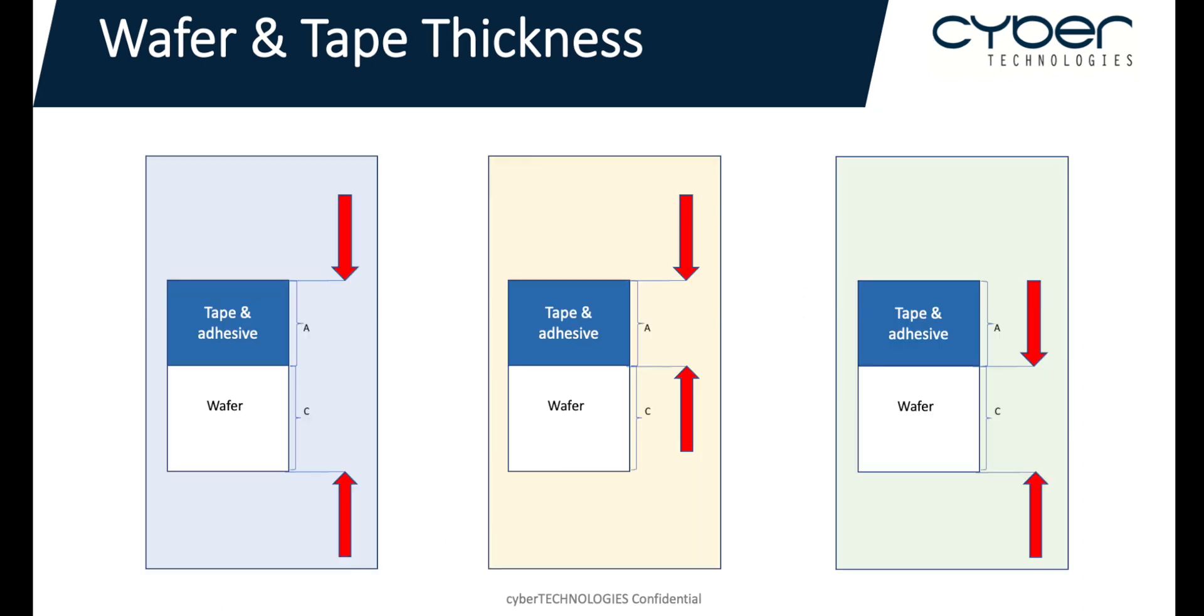In order to accurately measure the wafer, we perform two separate scans: one of the total thickness including the tape, and a second of just the tape layer itself, while factoring in the tape's refractive index. From these scans, we can then have ASCAN automatically subtract the tape thickness from the total thickness, resulting in the real actual thickness of just the wafer.